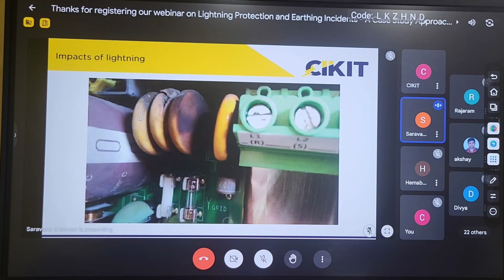From this damage and from the fuse we understood that the damage was caused mainly by the lightning impulse current, even though they had also ensured a lightning protection system for this building. The count was defined on the lightning event counter. The initial reading was around 12, and after this failure they checked the count and it was around 13. So they confirmed that lightning happened on that building, and only after that lightning did the failure happen. During the lightning, because of some kind of induction, the surges entered the equipment and the equipment failed. This kind of failure can be avoided by installing suitable surge protection devices.